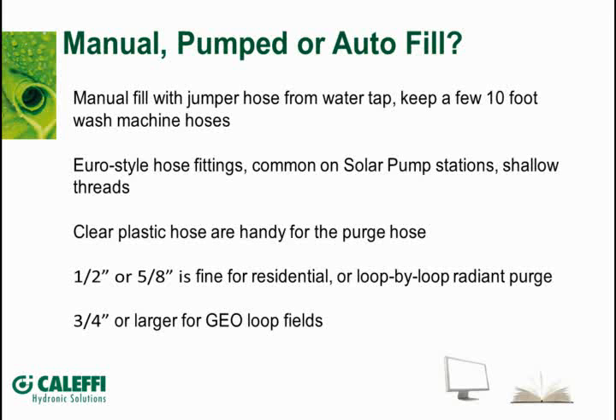Manual fill systems. Now, manual fill is typically when you're going to put a chemical or a glycol in the system. Obviously, it's not going to come out of the water pipe in your house, so you're going to have to pump that into a system. Now, small systems, you might be able to do that with a little hand pump. I'll show you some of the pumps that I've got that I've used. I make up a little assembly of different size jumper hoses, washing machine hoses, different hoses I've built with different connections on the end that I can get into the system and pump it in and also purge it out.